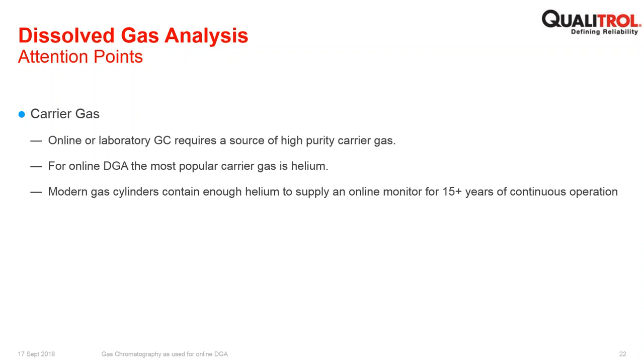For online DGA, the most popular carrier gas is helium. While this needs to be provided and managed, in actual fact, modern gas cylinders contain enough helium to supply an online monitor for about 15 years, and that would be at a 6-hour measurement cycle. If you move to an 8-hour measurement cycle, it would supply gas enough for 18 years. So the provision of gases needs to be managed, but it can be managed on day one when you're installing the monitor, to provide what will likely be a lifetime of gas.